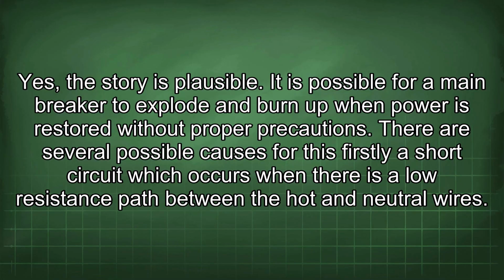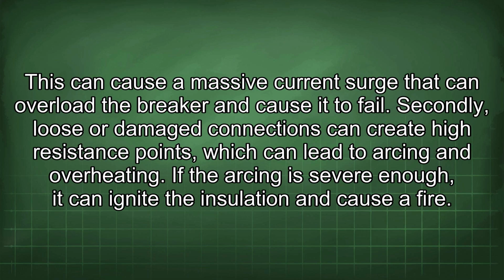Yes, the story is plausible. It is possible for a main breaker to explode and burn up when power is restored without proper precautions. There are several possible causes for this. Firstly, a short circuit, which occurs when there is a low resistance path between the hot and neutral wires. This can cause a massive current surge that can overload the breaker and cause it to fail.